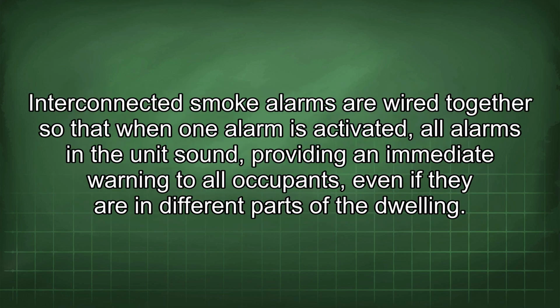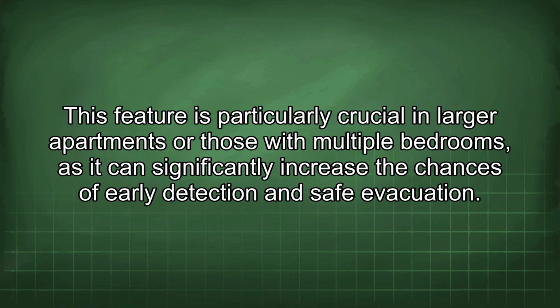Furthermore, NFPA 72 addresses the issue of interconnected smoke alarms, which are highly recommended, especially in multi-story dwellings or apartments. Interconnected smoke alarms are wired together so that when one alarm is activated, all alarms in the unit sound, providing an immediate warning to all occupants, even if they are in different parts of the dwelling. This feature is particularly crucial in larger apartments or those with multiple bedrooms, as it can significantly increase the chances of early detection and safe evacuation.